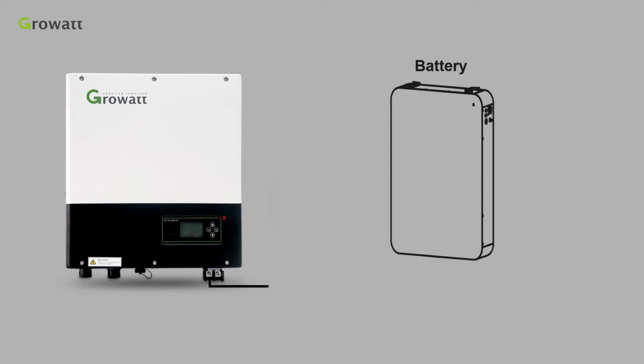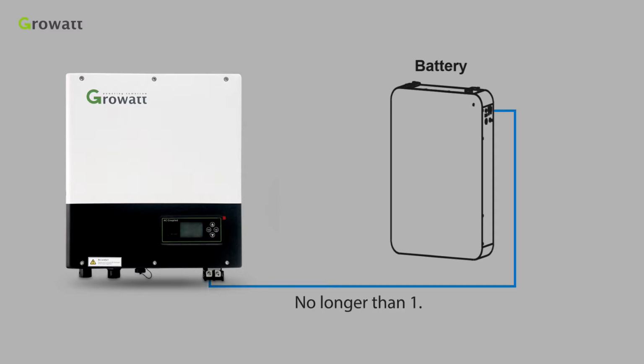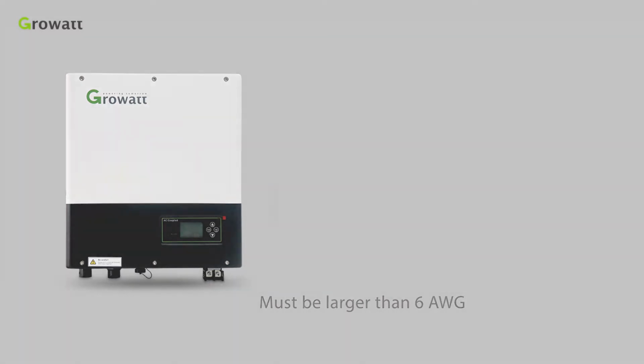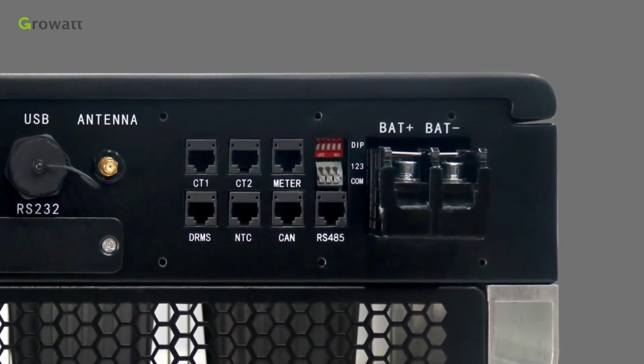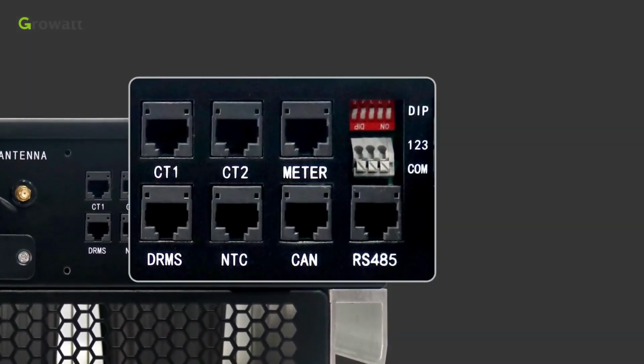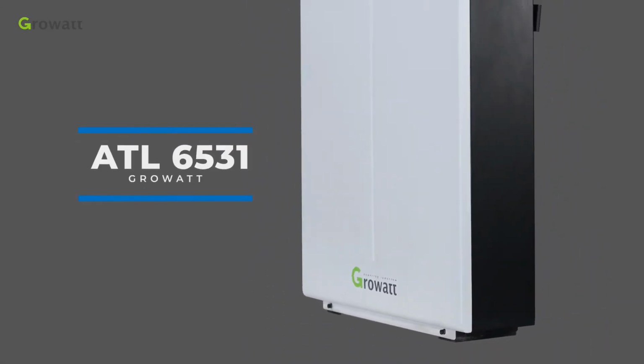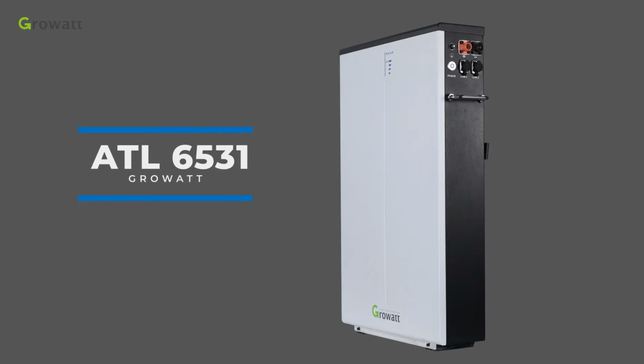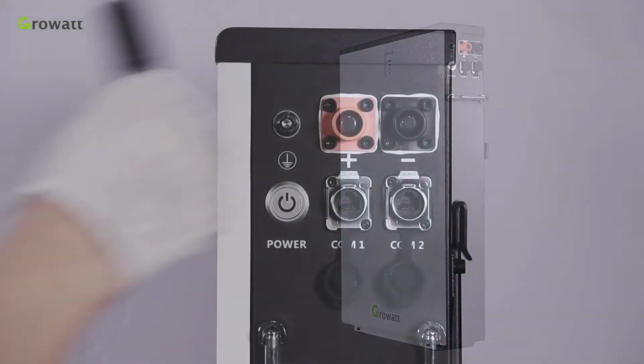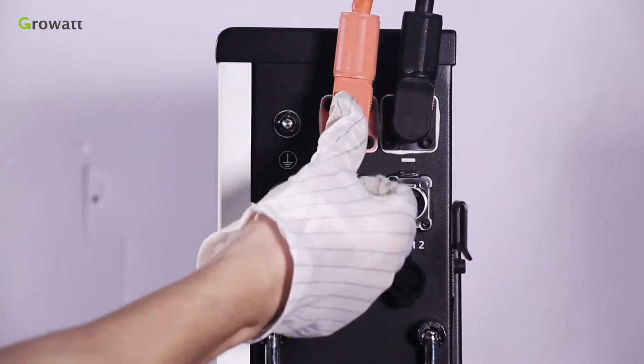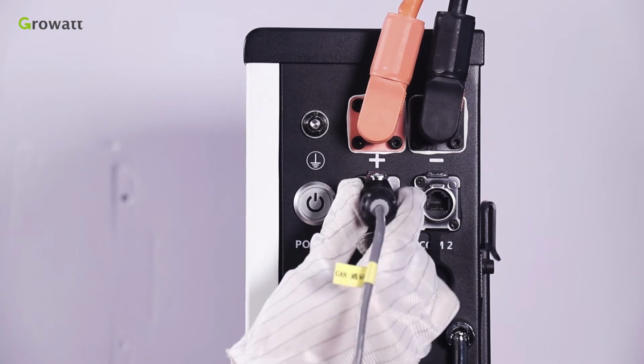When we make the battery terminal connection, the suggested distance between the battery and the SPA series is no longer than 1.5 meters, and the power line area must be larger than 6 AWG. As mentioned before, SPA has series communication terminals. In this video, we chose the ATL6531 pack to store the power. It has plug-and-play function. The connection with the battery is simple. We just need to insert the positive and negative power lines and the communication line to the battery ports.